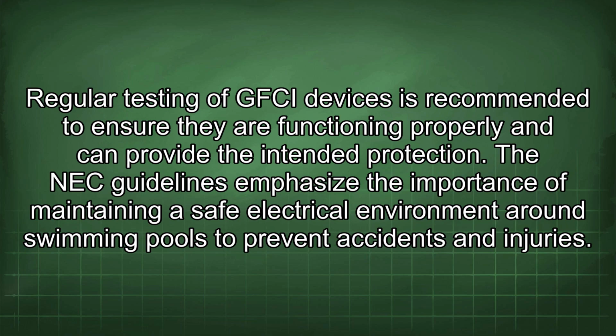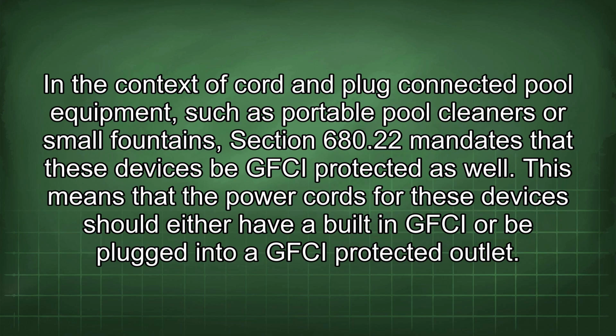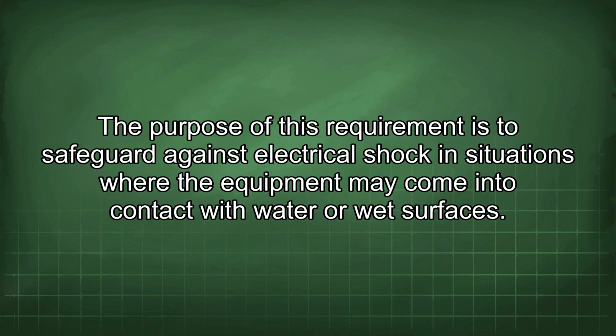Regular testing of GFCI devices is recommended to ensure they are functioning properly and can provide the intended protection. The NEC guidelines emphasize the importance of maintaining a safe electrical environment around swimming pools to prevent accidents and injuries. In the context of cord and plug-connected pool equipment, such as portable pool cleaners or small fountains, Section 680.22 mandates that these devices be GFCI protected as well. This means that the power cords for these devices should either have a built-in GFCI or be plugged into a GFCI protected outlet. The purpose of this requirement is to safeguard against electrical shock in situations where the equipment may come into contact with water or wet surfaces.